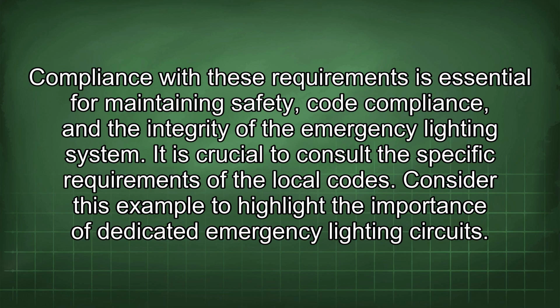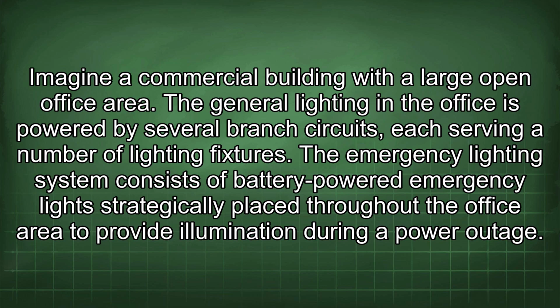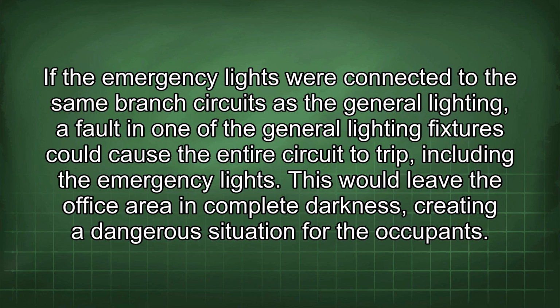Consider this example to highlight the importance of dedicated emergency lighting circuits. Imagine a commercial building with a large open office area. The general lighting in the office is powered by several branch circuits, each serving a number of lighting fixtures. The emergency lighting system consists of battery-powered emergency lights strategically placed throughout the office area to provide illumination during a power outage. If the emergency lights were connected to the same branch circuits as the general lighting, a fault in one of the general lighting fixtures could cause the entire circuit to trip, including the emergency lights. This would leave the office area in complete darkness, creating a dangerous situation for the occupants.